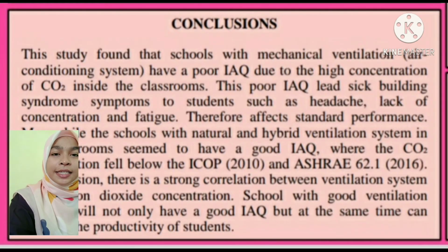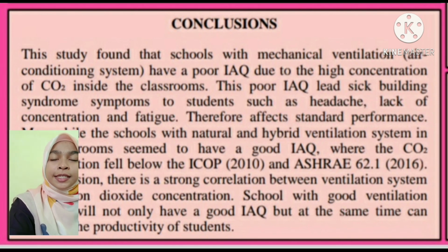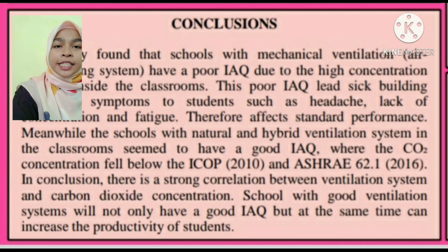This study found that the schools with mechanical ventilation, which is the air conditioning system, have poor indoor air quality due to high concentration of carbon dioxide inside the classroom. This poor IAQ leads to sick building symptoms in students such as headache, lack of concentration and fatigue, therefore affecting student performance. Meanwhile, the schools with natural and hybrid ventilation systems in the classroom seem to have good indoor air quality, where the concentration of carbon dioxide fell below the ICOP and ASHRAE standards.